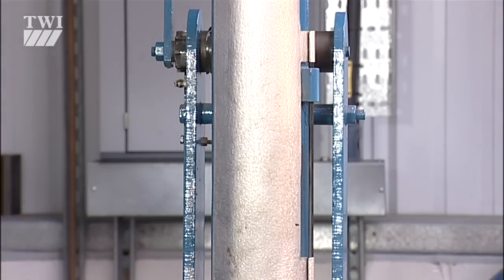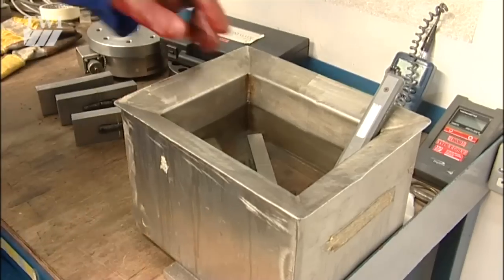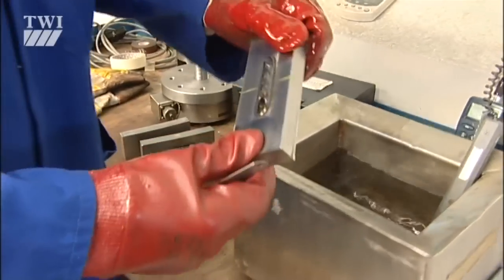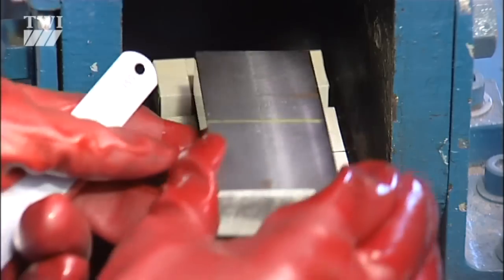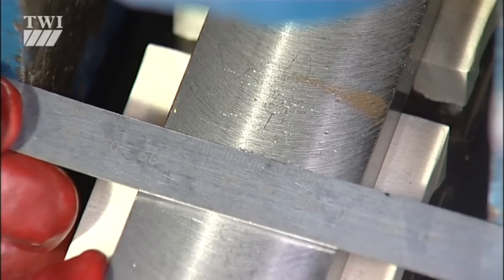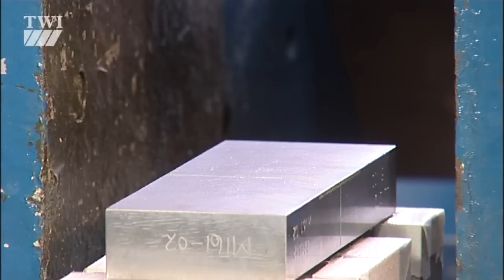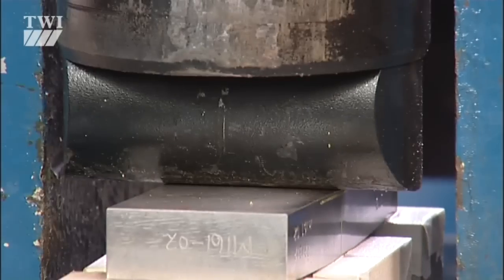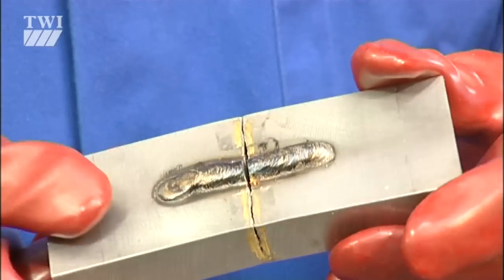Typical of these is the Nil Ductility Temperature Test. It's confusingly dubbed the NDT Test. The sample size is standardised, depending upon plate thickness. A brittle crack is introduced on one side, and the simply supported specimen is struck in a standard way. The test is carried out on a number of specimens at progressively lower temperatures, until the test piece breaks in a brittle fashion. This is known as the Nil Ductility Temperature, or NDT.